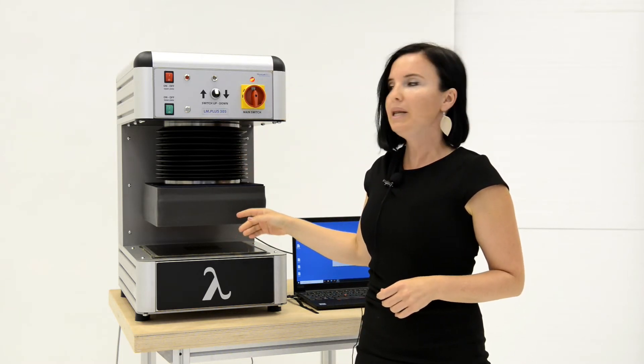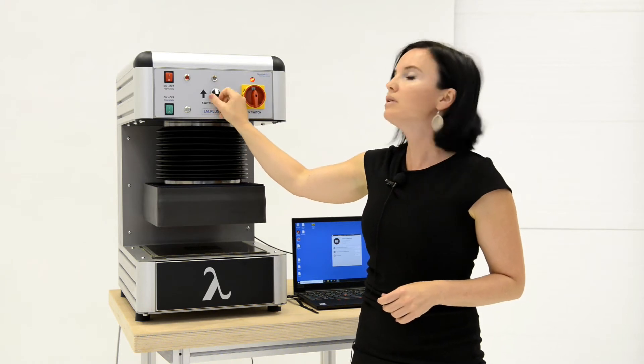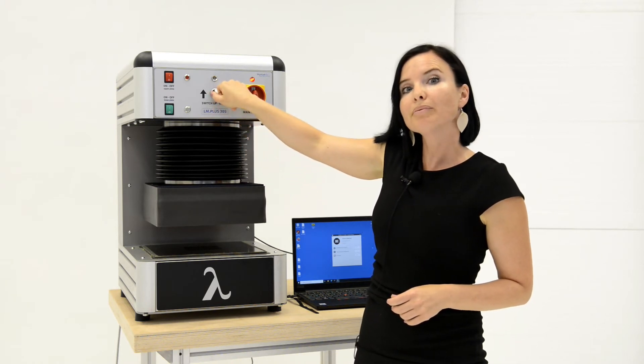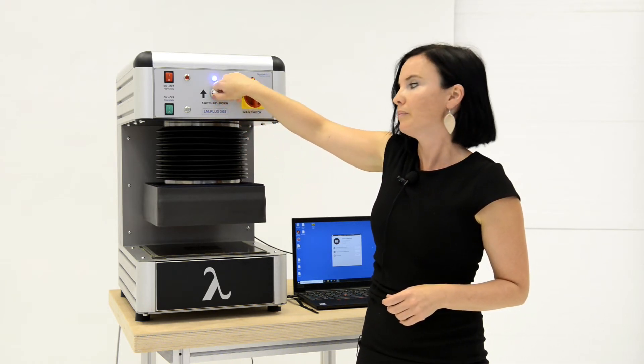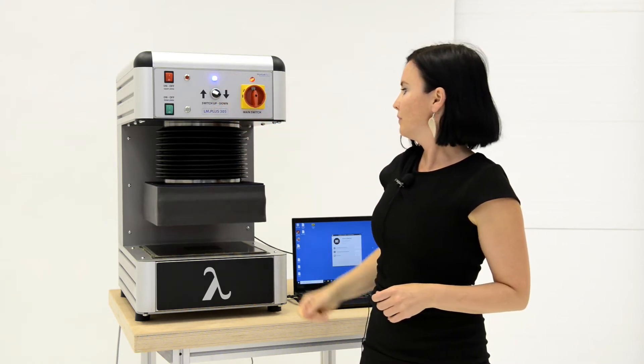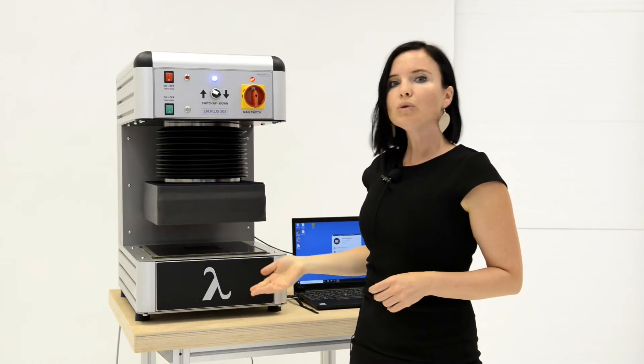Lift the upper plate by turning the middle switch up. It will start going up and stop automatically when it reaches its top position. It is very important for accurate thickness measurement.